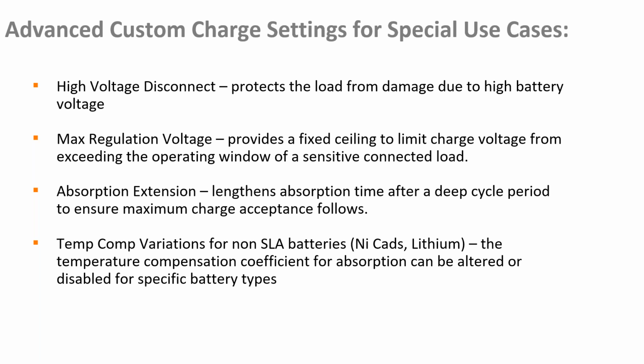And then absorption extension is really more of a feature geared toward lead acid batteries, just because there is sort of an associated memory effect with the depth of discharge, which, as Alex mentioned, you don't get with lithium. It's very stable throughout. But with lead acid, if you went through a deeper discharge cycle one day, down to 30% state of charge, down to 12 volts, you're going to want to be able to extend the absorption period the following day in order to recover that lost capacity. So there's no long-term lasting memory effect. That's what that setting is responsible for.